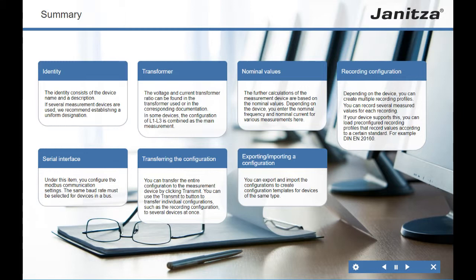Recording Configuration: Depending on the device, you can create multiple recording profiles and record several measured values for each recording. If your device supports it, you can load pre-configured recording profiles that record values according to a certain standard — for example, DIN EN 50160. Serial Interface: Under this item you configure the Modbus communication settings; the same baud rate must be selected for all devices in a bus. Transferring the Configuration: You can transfer the entire configuration to the measurement device by clicking Transmit, or use Transmit To to transfer individual configurations — such as the recording configuration — to several devices at once.